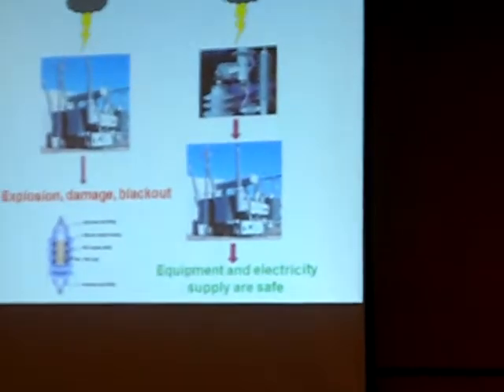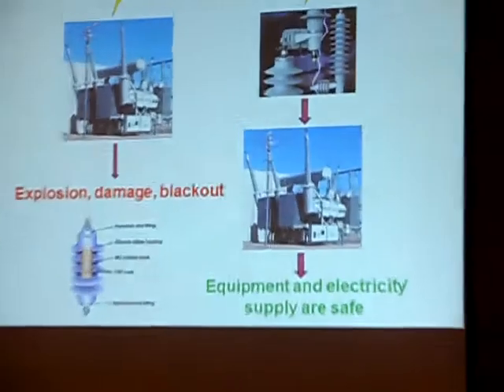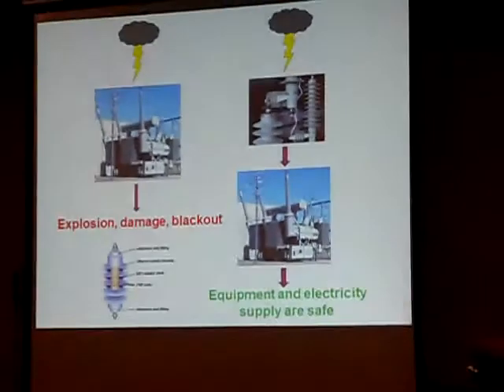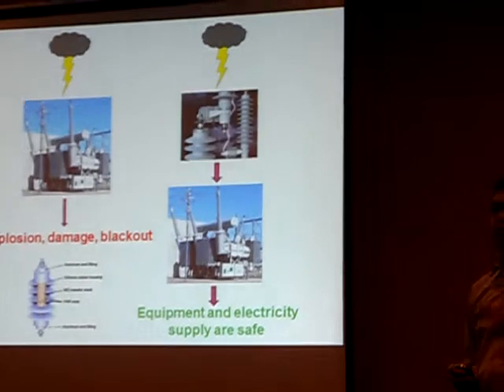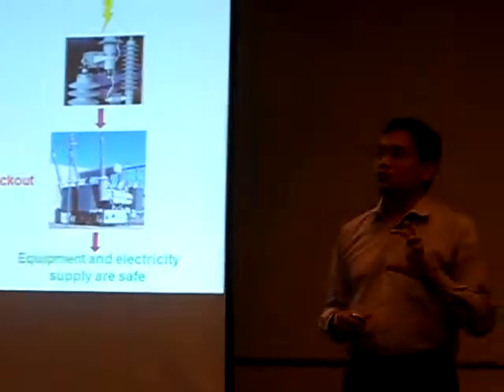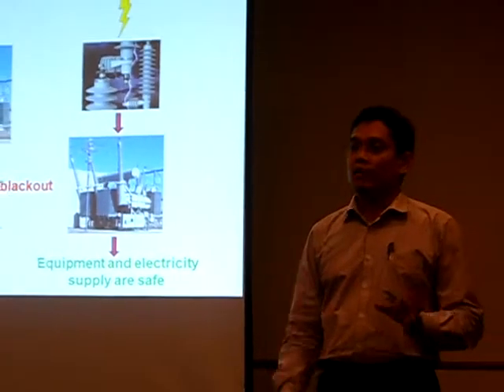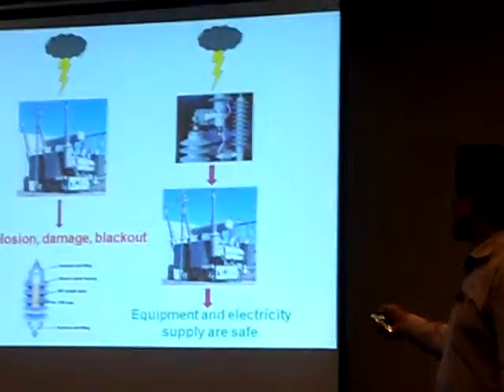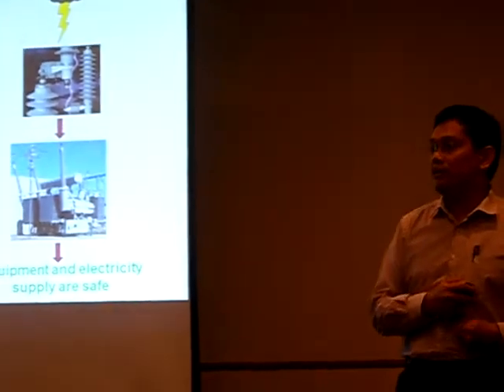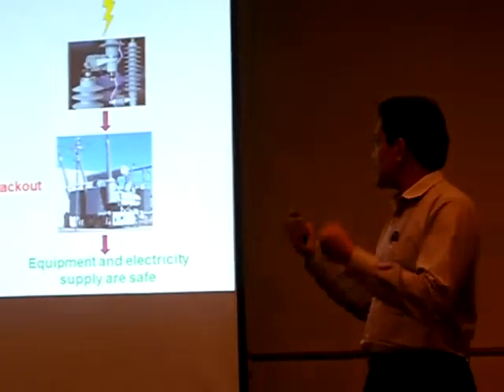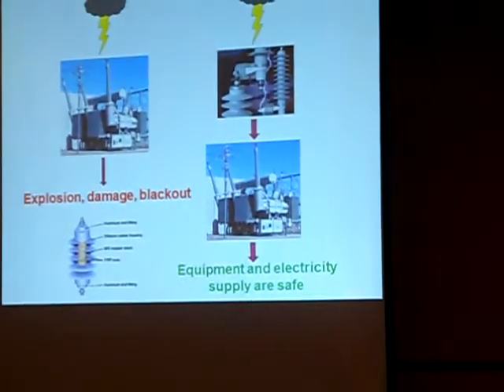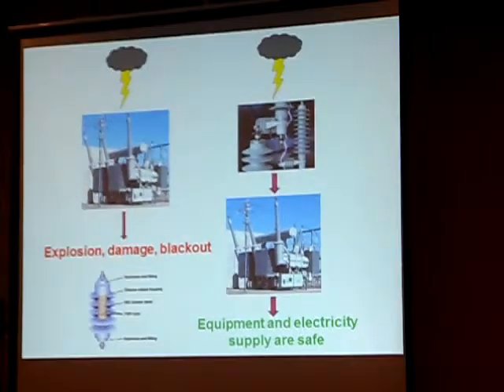If you wonder what an arrestor looks like, it has a stack of zinc oxide within its body, where it behaves like a diode. Under normal operation it's connected to the high voltage line and draws a certain leakage current. But when a lightning surge comes into the system, before it reaches the transformer, it gets short-circuited to the ground, arresting all the energy to ground, giving you equipment safety as well as no blackouts.